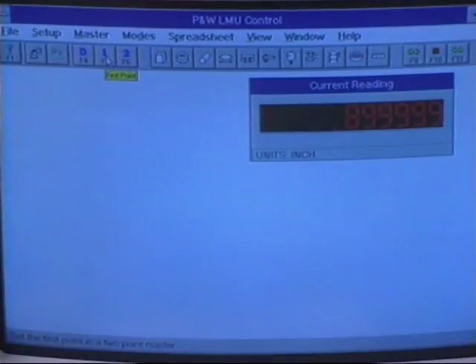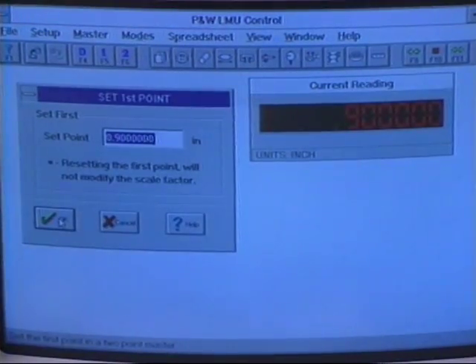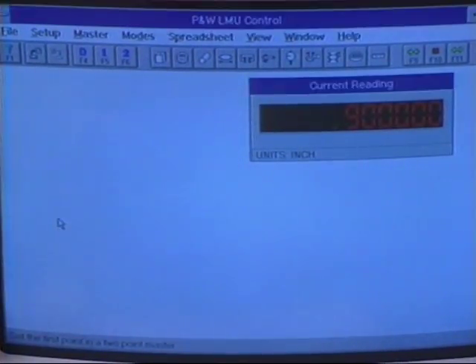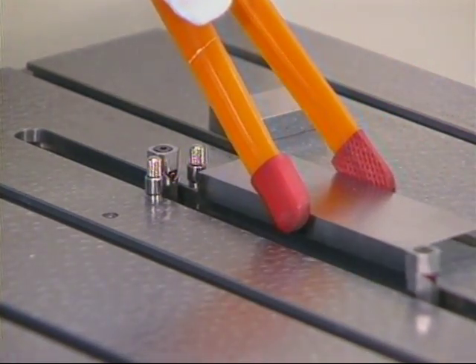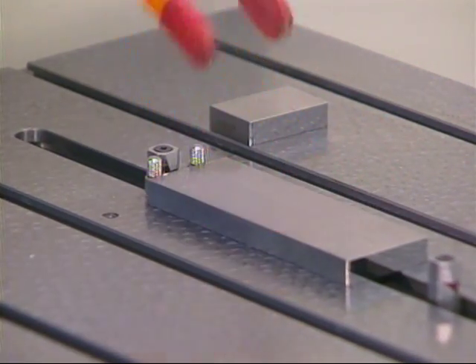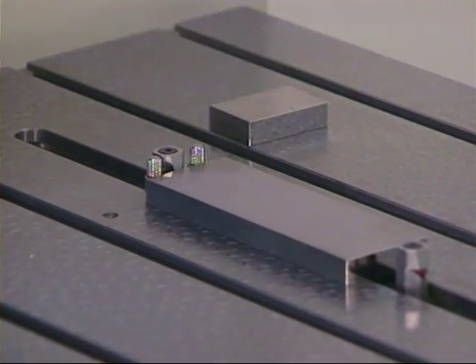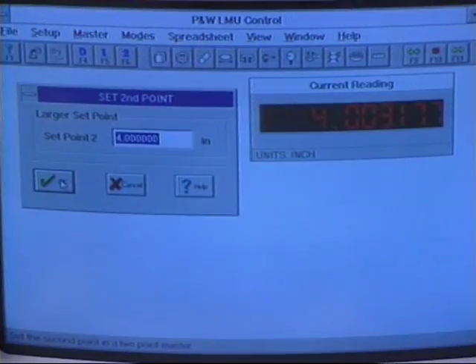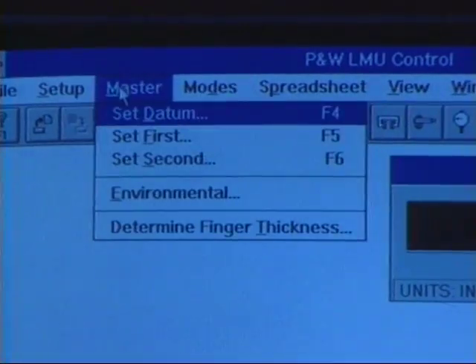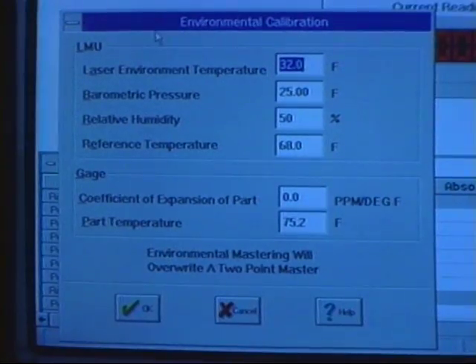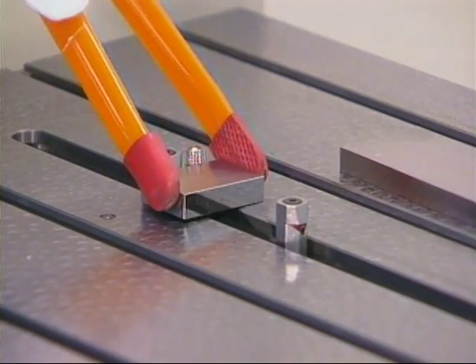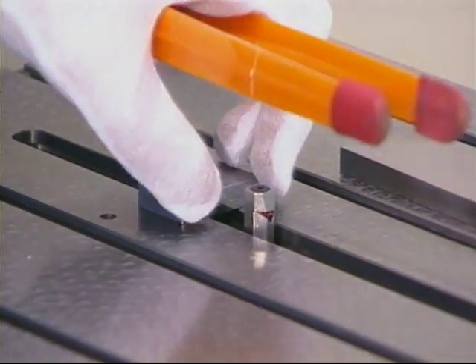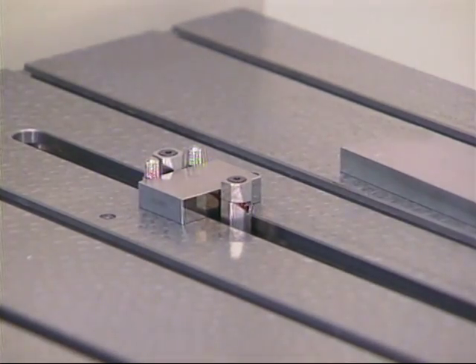Once engaged, key in the value of the block. Next, open the probes and replace the gauge block with yet another larger gauge block. Close the probes and key in the value of the block. Alternatively, if environmental and gauge material data are available, the system can be mastered by using a single gauge block. You're now ready to measure.